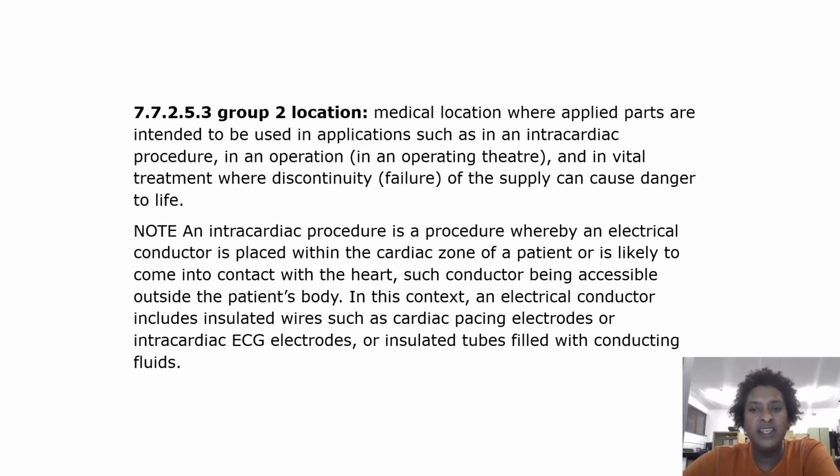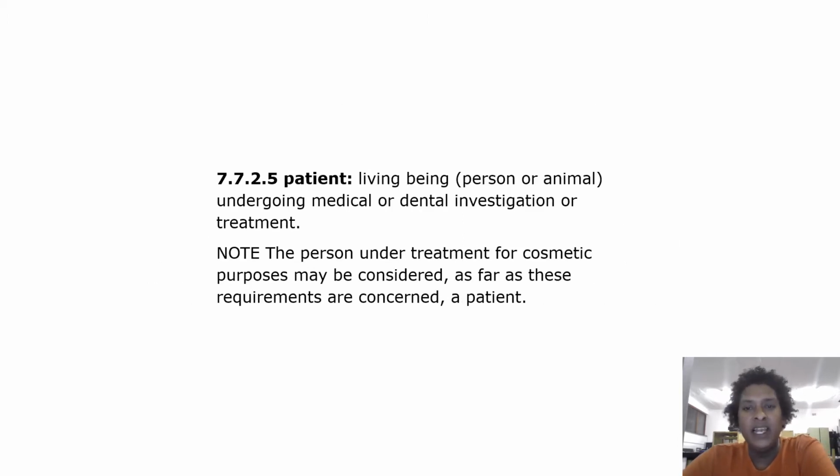In this context, an electrical conductor includes insulated wires such as cardiac pacing electrodes or intracardiac ECG electrodes, or insulated tubes filled with conducting fluids. Patient, living being, person or animal undergoing medical or dental investigation or treatment. Note, the person under treatment for cosmetic purposes may be considered, as far as these requirements are concerned, a patient.